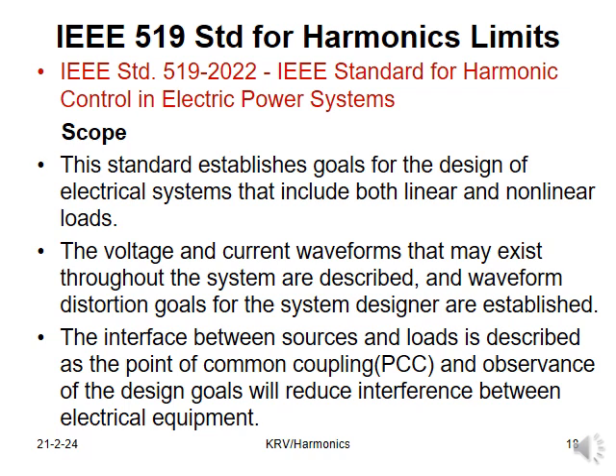The most widely referred and followed standard globally is the IEEE 519 standard for harmonics limits. IEEE standard 519-2022 is the latest version of this standard, which is titled IEEE Standard for Harmonic Control in Electric Power Systems. The scope of this standard is: this standard establishes goals for the design of electrical systems that include both linear and nonlinear loads. The voltage and current waveforms that may exist throughout the system are described, and waveform distortion goals for the system designer are established. The interface between sources and loads is described as the point of common coupling (PCC), and observance of the design goals will reduce interference between electrical equipment.